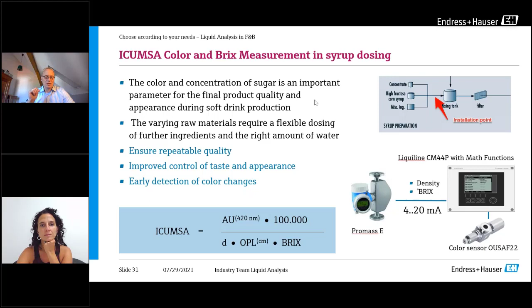The nice point is that with the Promass, based on the Coriolis principle, we can also measure the density and the Brix. This goes over the 4 to 20 milliampere output directly into the Liquiline, where it's calculated with math functions using the direct equation. This way we can ensure repeatable quality and improve taste and appearance, and whenever something happens in the raw materials or during filling, we can directly detect any changes. So that covers a couple of examples of different hygienic processes.